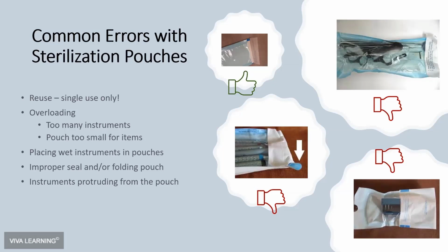These are errors with the sterilization pouches: not folding them properly, reusing them, too many instruments in the pouch. So if you have a lot of overlapping instruments, then maybe you're not going to get appropriate steam penetration on all those instrument surfaces. We talked about wet instruments, improperly folding or sealing the pouch. We should never have anything penetrating outside of the pouch. And although the temptation is, as you can see on the lower right-hand side with this burr block, the temptation is to fold it over, make it more compact. We've just now covered up the indicators on that pouch.